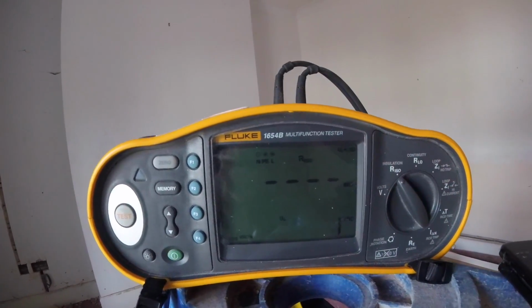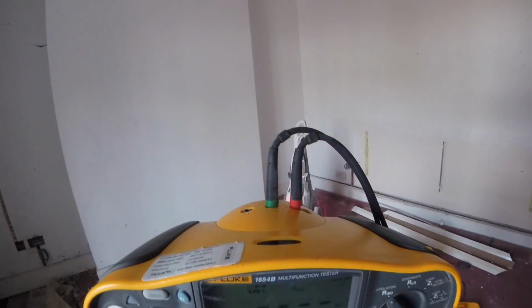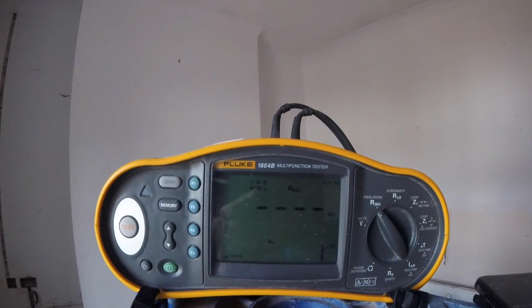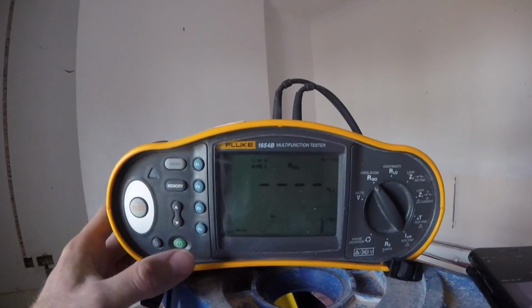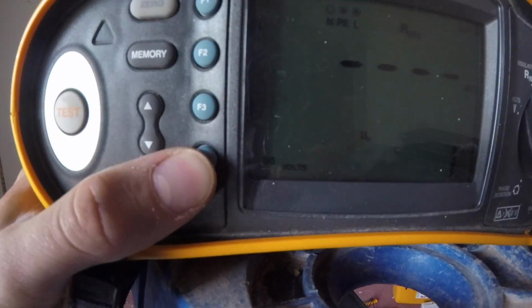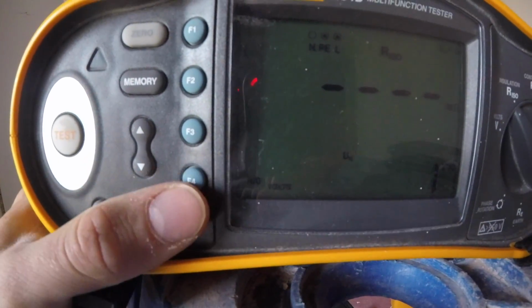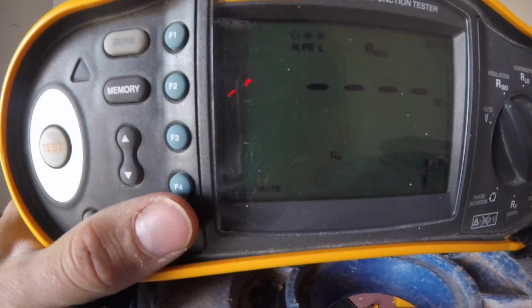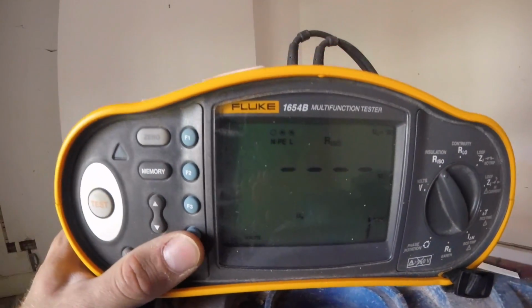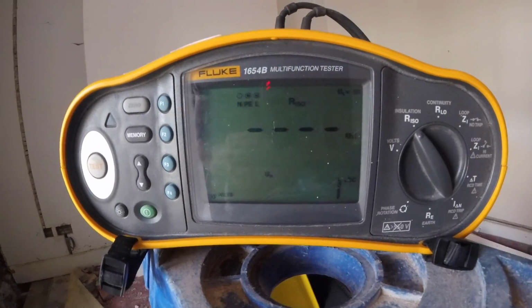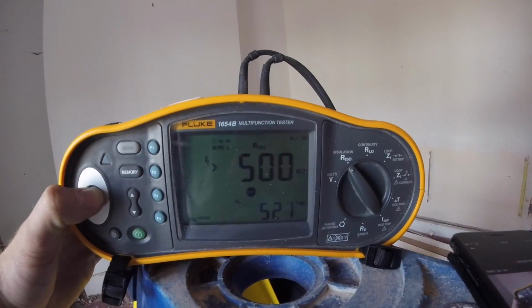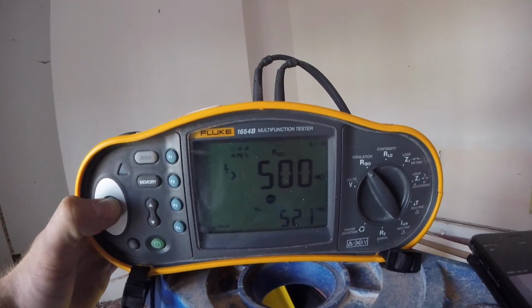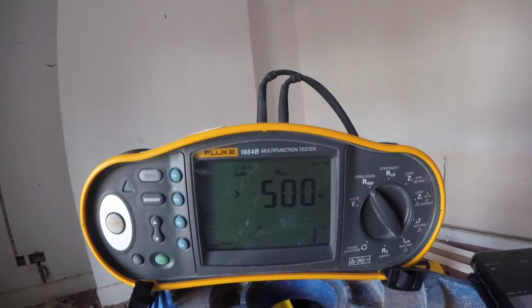Next test is the insulation resistance. So you set your dial onto insulation resistance, plug in your two probes. So I've plugged in my red and green earth probe, and you'd literally just put them on two conductors, select the voltage you want. So you start off on 50 volts, 100 volts, 250 volts, 500 volts and 1000 volts. Generally I test on 500 volts, obviously depending on the circuit I'm testing. Press test, and in an ideal situation it should come up with greater than 500 megohms, so that circuit would be in fact clear.